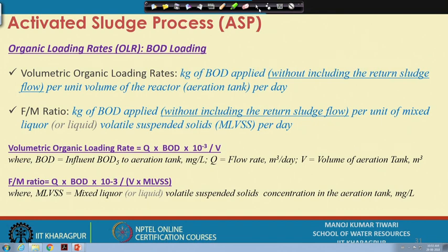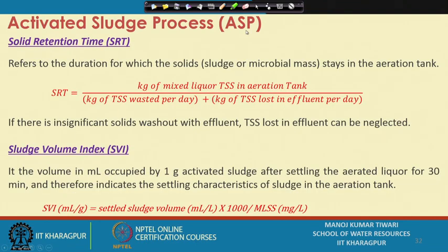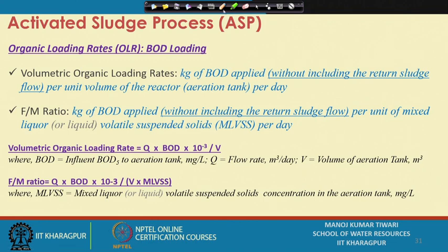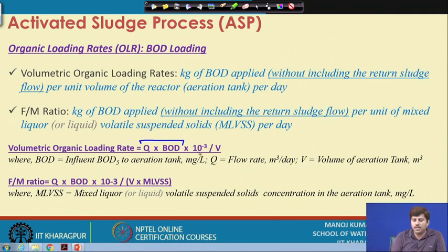Then there is volumetric organic loading rate. From here we can get the amount of BOD applied. So, how much BOD is applied? If Q is the discharge, so Q into BOD will be the mass of BOD. Okay.